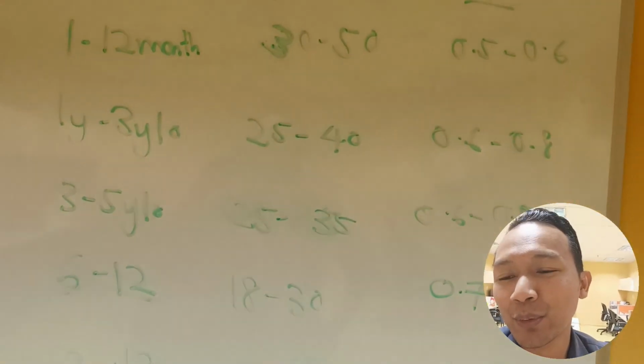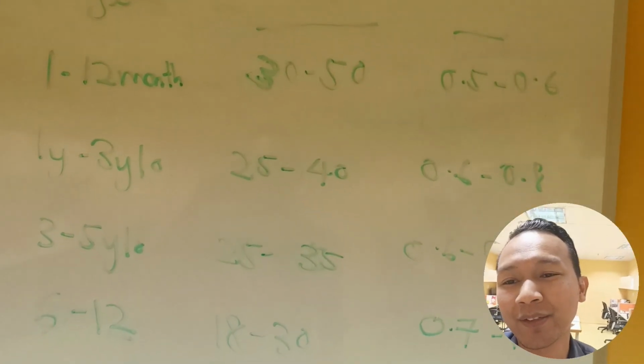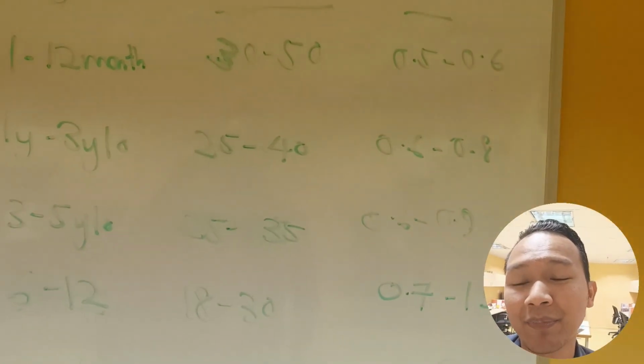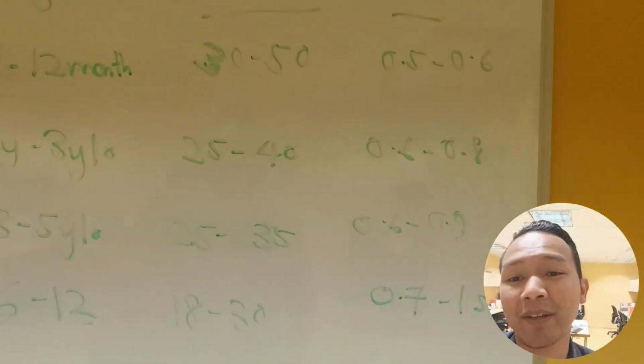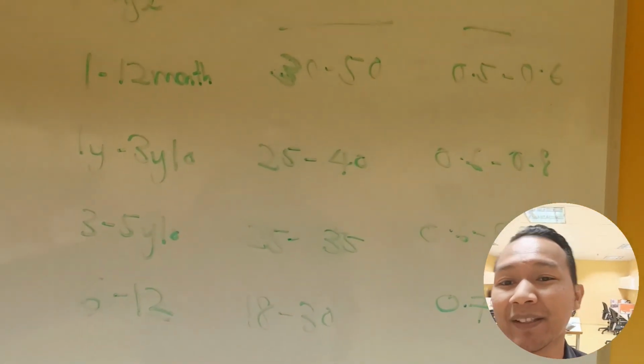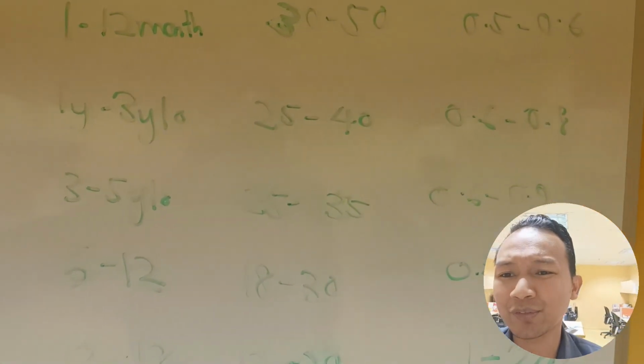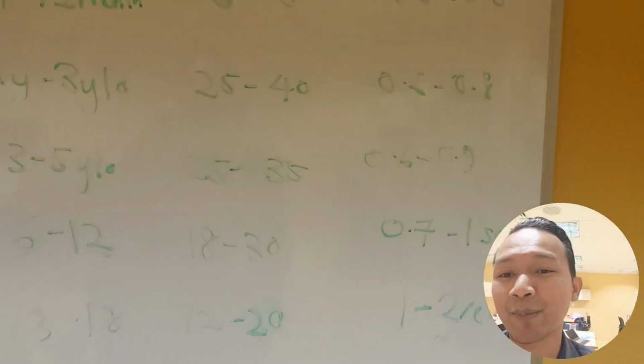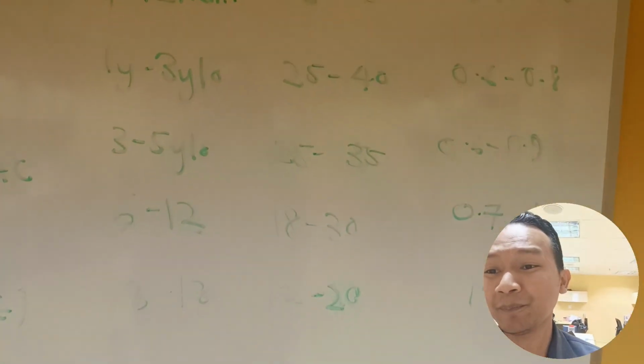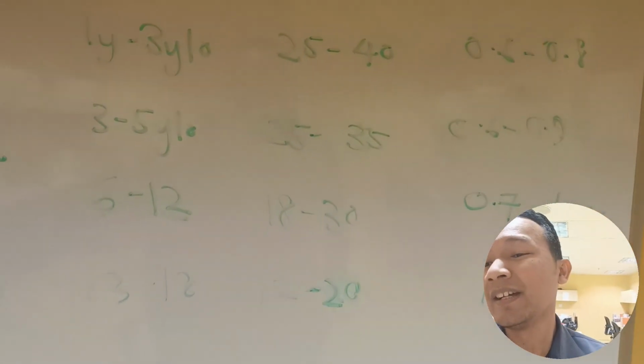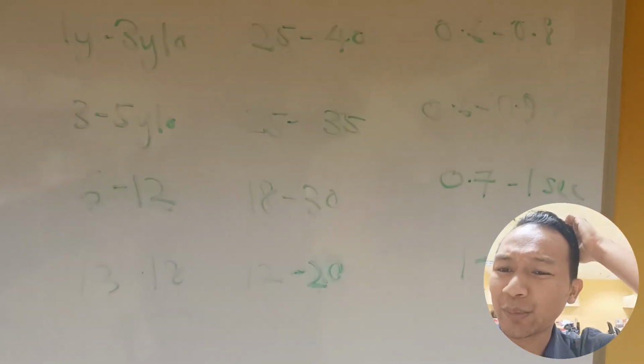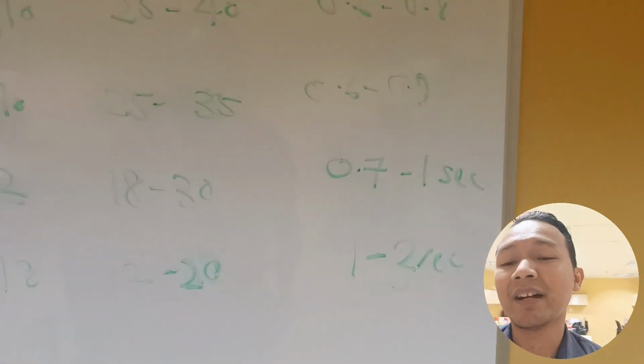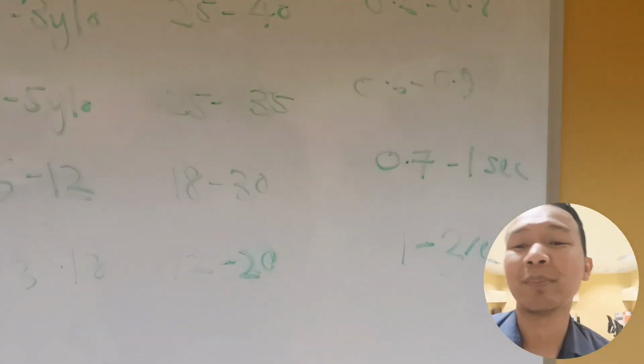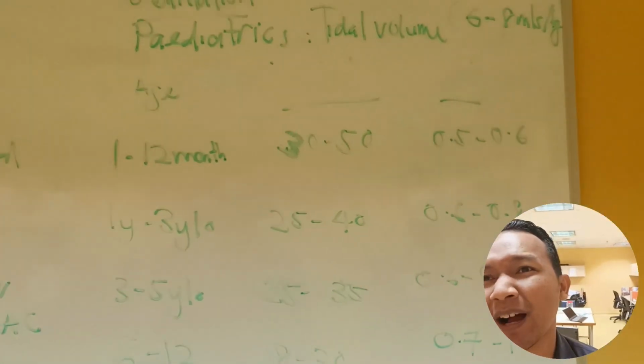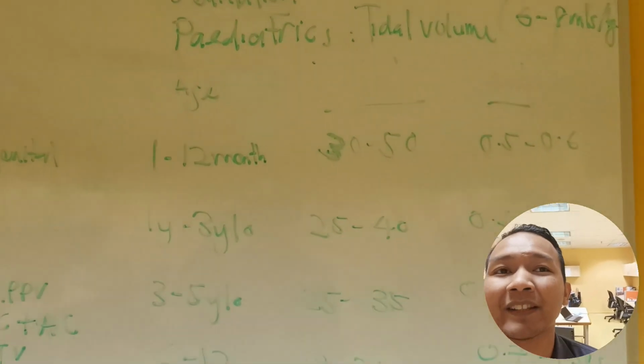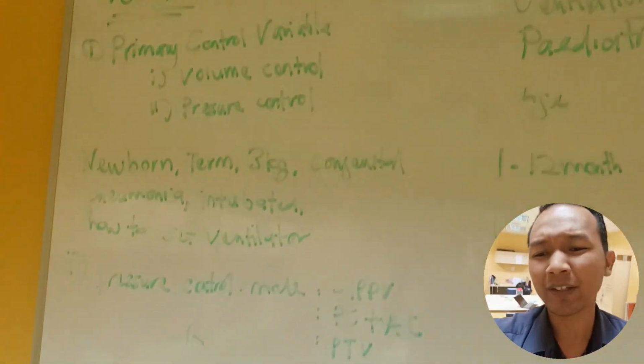For 3 to 5 years old, the rate can be around 25 to 35, depends on the size. The eye time, inspiratory time, is about 0.6, can be up to 0.8, up to 0.9, also still acceptable depending on the size. For 5 to 12 years old, the rate is 18 to 30, the eye time about 0.7 to 1 second depending on the size as well. And teenagers or big adolescents, like adults already lah, 13 to 18, you set 12 to 20. The eye time can be 1 to 2 seconds at most. Alright, so that's basically how you set the ventilator for the eye time and rate. Basically the pressure, the mode, everything's about the same lah.